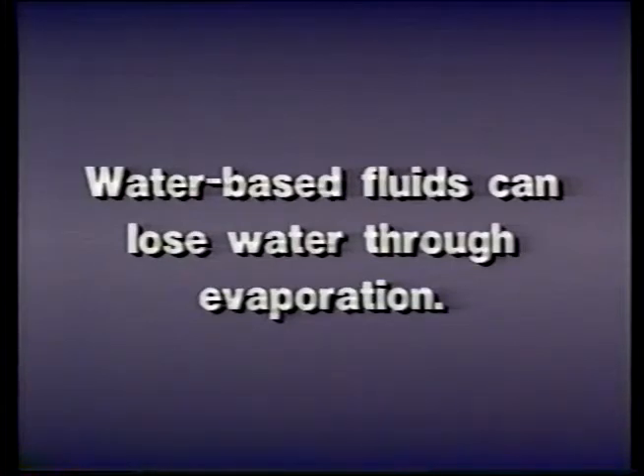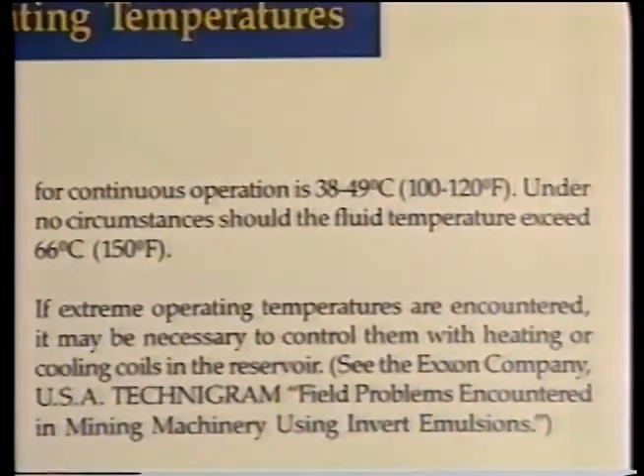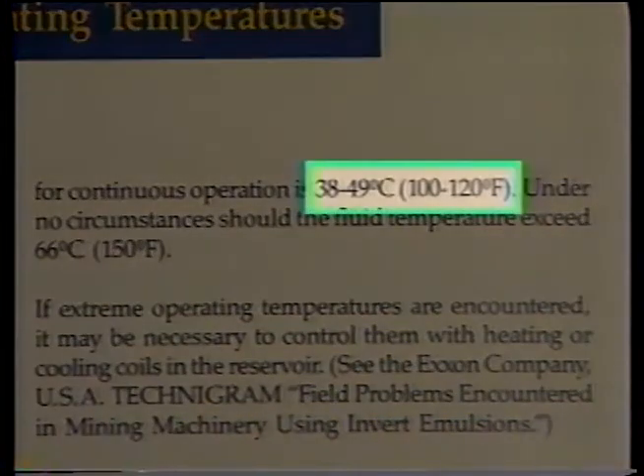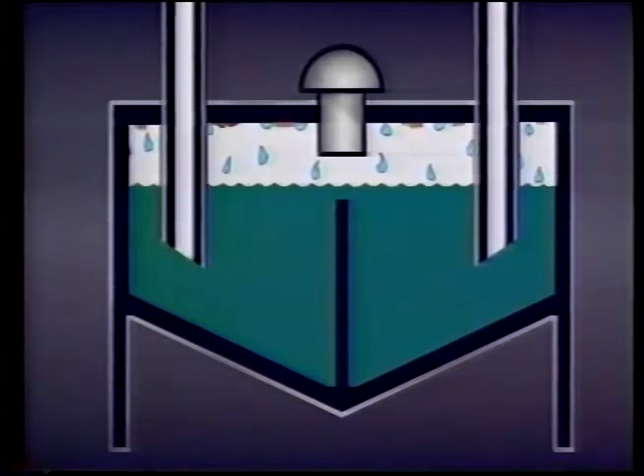A common disadvantage of all water-based fluids is their tendency to lose water through evaporation. That's why most water-based fluids are recommended for use at temperatures below 140 degrees Fahrenheit — 120 degrees is the most common recommended maximum. Water evaporation from these fluids can cause several problems. Water vapor escaping from the fluid can condense on unprotected metal surfaces causing rust. Eventually particles of rust will flake off and contaminate the entire system. Many water-based fluids contain rust inhibitors but over time rust will occur anyhow.